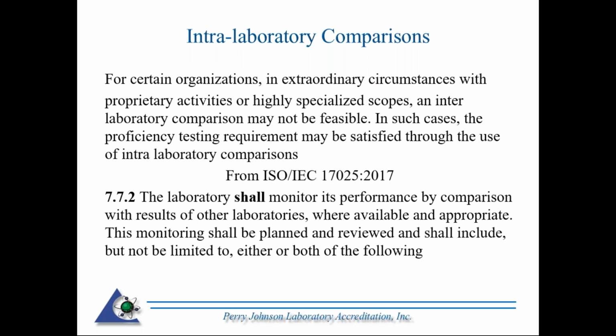So I think our policy, when 17025 was revised, you can see what's required there in 7.7.2. It's basically stating, and there's a 'shall' there, you shall monitor your performance by comparisons with results of other laboratories, where available and appropriate. So if it's not, that's where you state your case, tell us why. This monitoring shall be planned and reviewed, and shall include, but not limited to, either or both of: third party proficiency testing or interlab comparison.